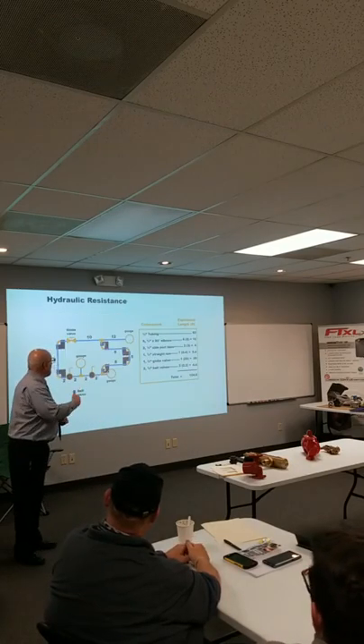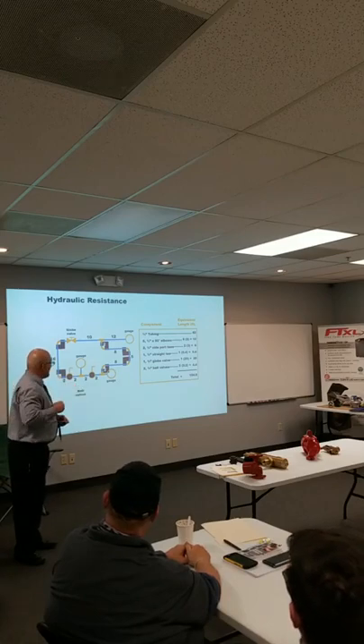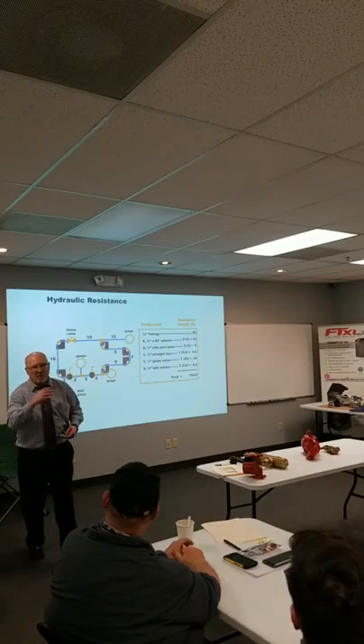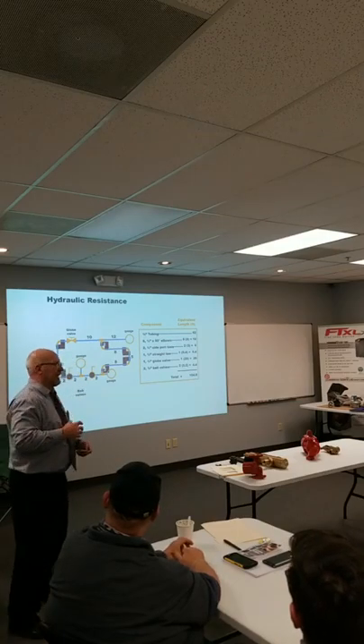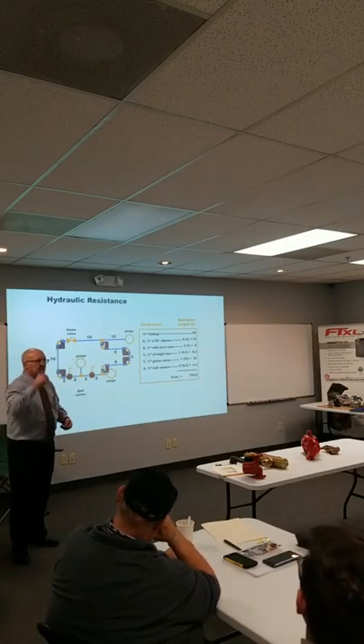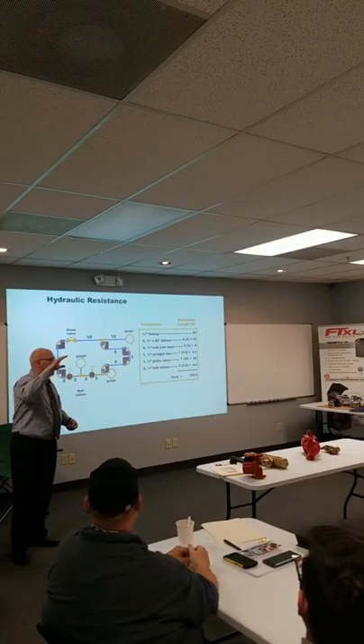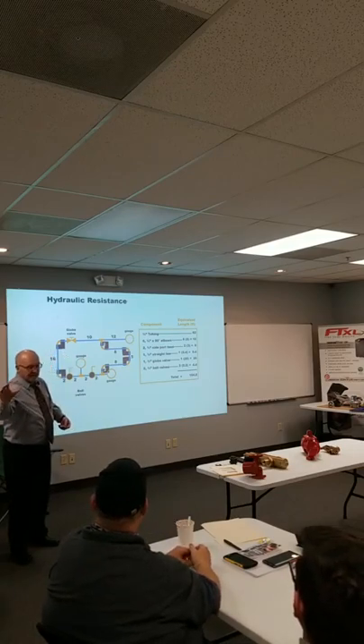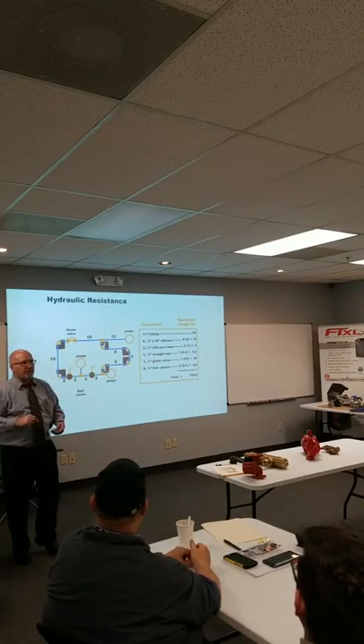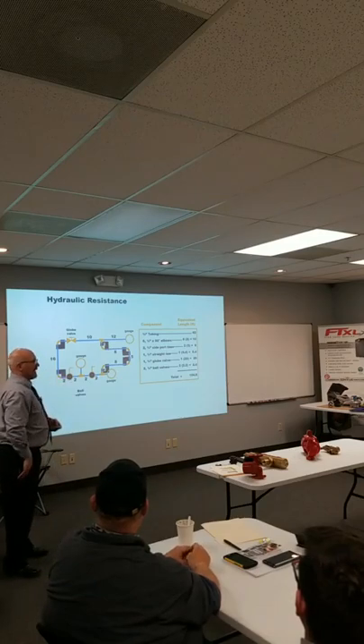So the point is everything has a pressure drop that we have to overcome. If I need 20 gallons a minute through that system, I have to be able to overcome all that resistance to get 20 gallons a minute. If I have more resistance, I'm not going to get 20 gallons a minute. A pump is a dumb animal. All it knows is it has to work on the pump curve. It doesn't care if it's down here or down here. The system is what determines where the pump runs. That's why you're balancing that discharge to bring that pump back on the curve.